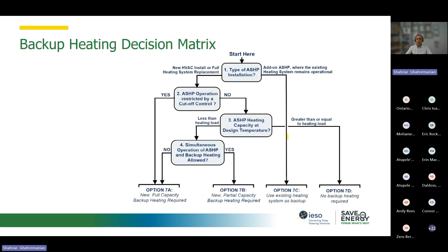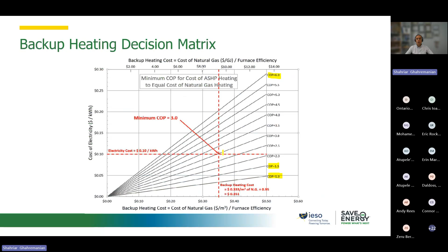So this is the graph that I told you before. Again, these are the heat pumps with different efficiency, from COP 1 up to a COP of 6, which is a more expensive one for sure. But again, the balance point can become different, and then we can have less extra heating or auxiliary heating for our facility actually.